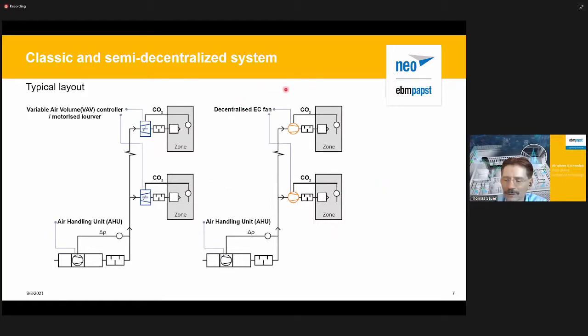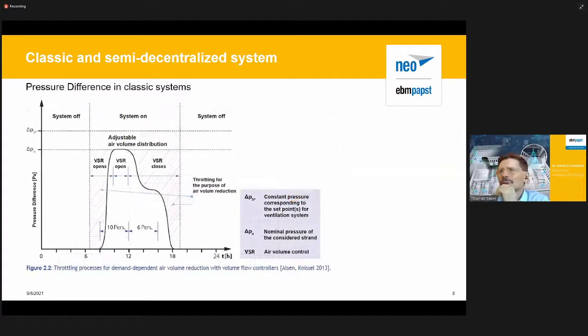If we look now at the decentralized system, that looks fairly similar. The only change is the place where the flaps are installed. We now have a fan installed, and the control is going to that fan. So why are we doing that? If we look at a typical system pressure, the differential pressure across the VAV box, we can see here the different settings. So we have no operation, then people come into the building, the VAV opens, and then it is maximum open. So we have the differential pressure between the main duct and the air duct that leads the air into the room. If there are fewer people in the room, the flap closes, and if there's no one in the room, the flap closes constantly.